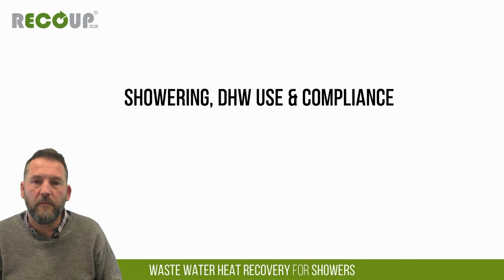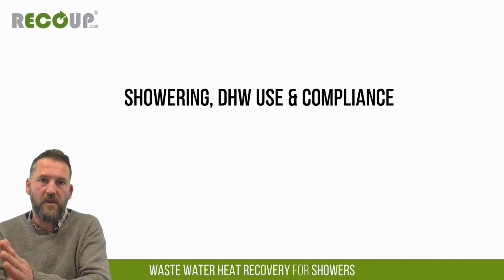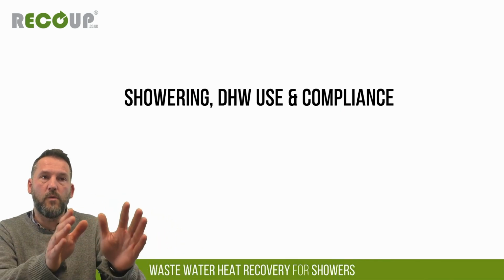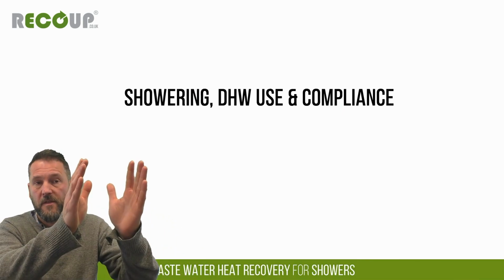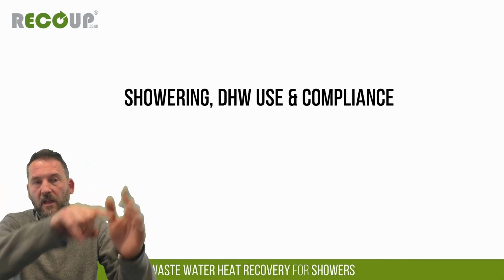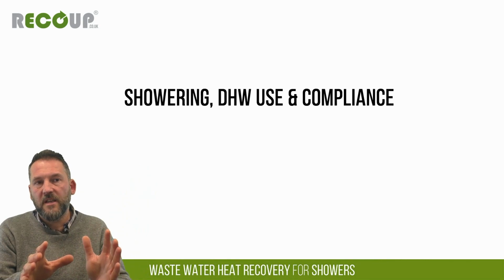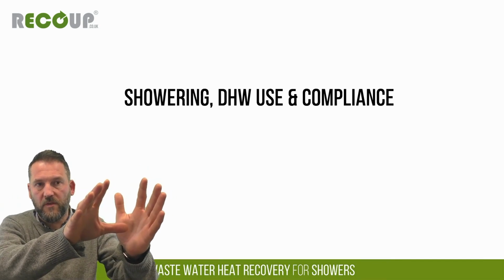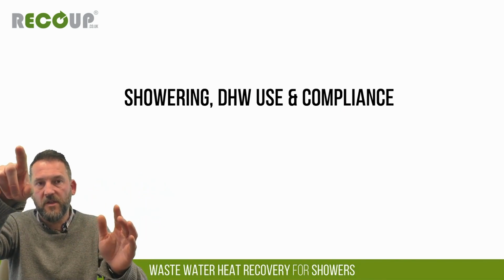So, question: vertical pipe system A, could then the preheated water be taken to other cold feeds in the dwelling, or is it limited to the shower tray it's installed for? No, it has to go to the cold side of the shower, and if it's system A, it's going back to the hot water source. So the cold water feed that would normally feed, for instance, the cylinder, will be routed through the wastewater heat recovery unit and back. It means that in practice, when the shower's on, that's when we're getting a preheated feed to the hot water system and back to the shower as well.